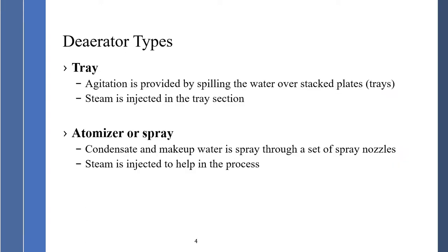There are two types of deaerators. One is a tray type — agitation is provided by spilling water over stacked trays, and steam is injected into the tray section to assist in the deaerator operation. The other is an atomizer or spray type, where condensate makeup water is sprayed through a set of spray nozzles and steam is injected to help in the process.